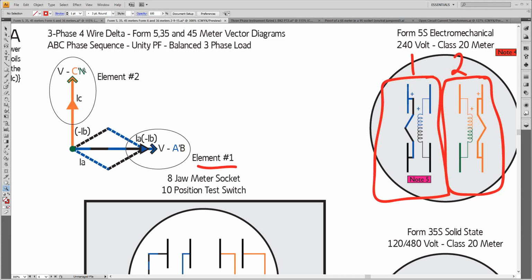C to neutral voltage is 86% of this voltage. This is 100% of this current, and so I get equal torque from each one of my meter elements. So that's what's happening with the 4-wire delta with the two CTs, one CT with A to B in it, the other CT with a high leg current or IC in it, A to B voltage across this potential coil, C to neutral across this potential coil.